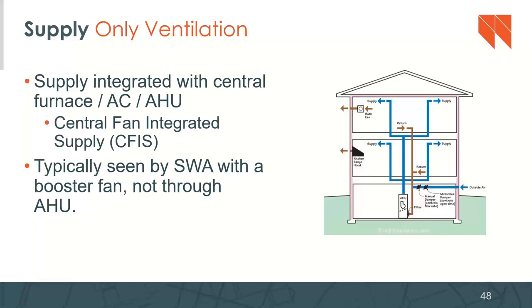Okay. So supply only. Supply only, remember, is pushing air into the building, into the dwelling unit. Usually it's integrated with a central furnace, an air conditioner, an air handler, something that is usually ducted to that air handler. And it's usually integrated with that supply fan. So this central fan integrated supply, abbreviated CFIS, is the most typical thing that we see for supply only. We usually see this happening with a booster fan though, not necessarily through the air handler.